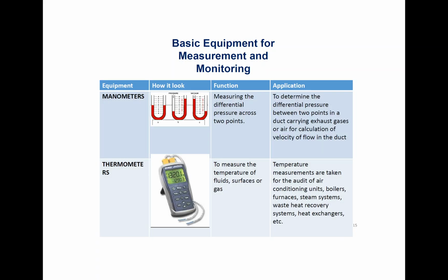Next is manometers. Its function is simple - to check the differential pressure between two points, for example how exhaust gases flow in the duct. So we use manometers to measure differential pressure between two points.